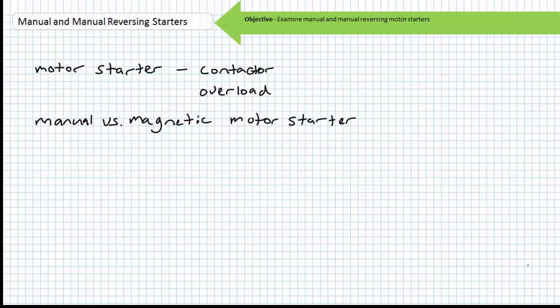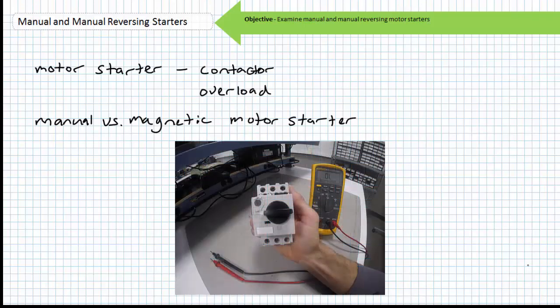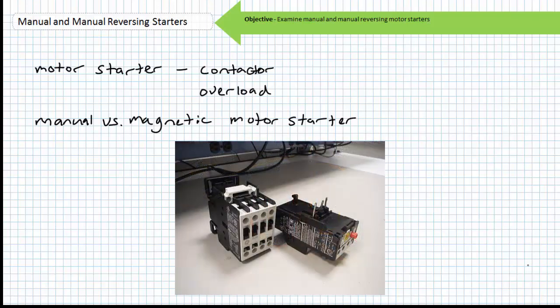As you'll recall, a contactor paired with an overload element formed the two necessary components for a motor starter: one, a means of starting or stopping the motor by making or breaking an electrical connection—the contactor—and two, a means of protecting the motor from sustained overload conditions—the overload. A contactor and overload can be integrated into a single package called a motor starter, or the pair working in combination can be considered a motor starter.